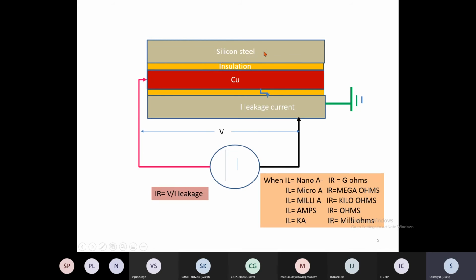So there are slots, or the windings are in the silicon steel, and as I told you, the insulation is not a perfect insulator. Some electrons will always leak, penetrate the insulation and come to the core, which is grounded. This core of all the transformer, generator, motor is connected to the ground. So these leaking electrons will migrate to the ground.